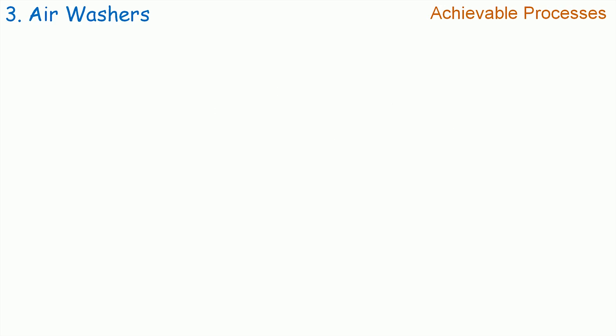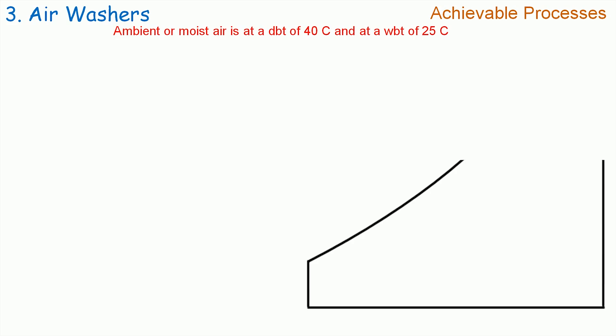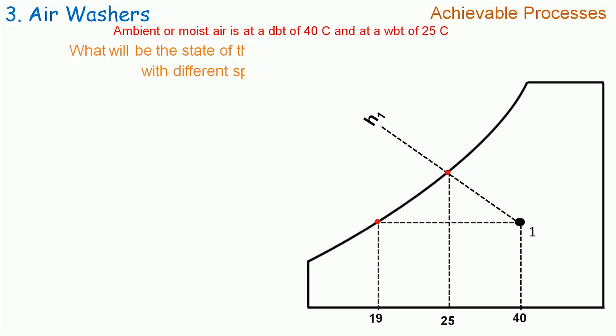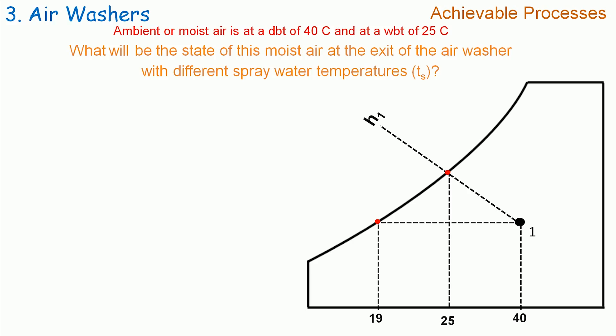Let us now look at the psychrometric processes that are achievable with air washers. Let us consider the moisture at DBT equal to 40°C and WBT equal to 25°C. We will plot this moisture on the psychrometric chart. The state point 1 denotes the moisture at 40°C DBT and 25°C WBT. We can read the dew point temperature corresponding to state point 1 as 19°C and let the enthalpy be H1. While keeping the state of the moisture unchanged, we will change the temperature of the spray water and see how the condition of air at the air washer exit will be changing. In other words, we will be populating this table.